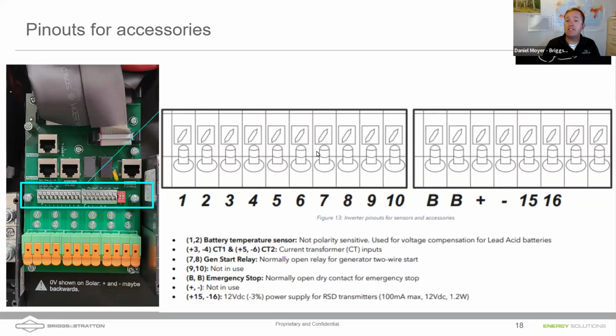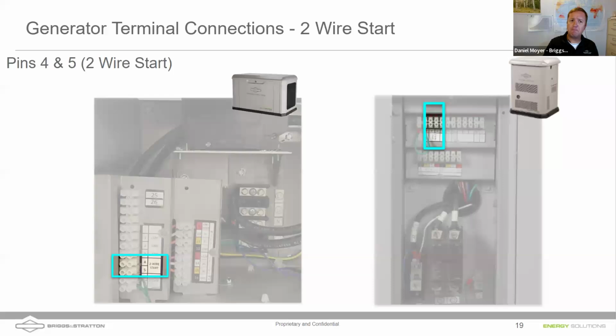Really, it's pins 7 and 8 here. This is where you'll send that signal to the generator to let it know to start up. This is normally open, and fortunately for us, Briggs and Stratton generators operate on a normally open gen start relay. There are some other companies that do a normally closed, and you may be able to get a device that can allow you to adjust that. So you come out of that Solarc with that 2-wire signal to start.